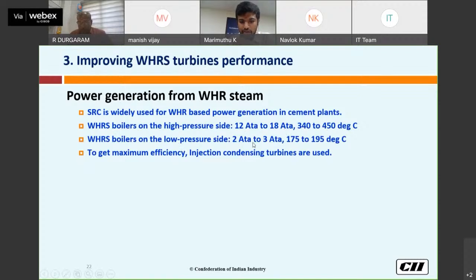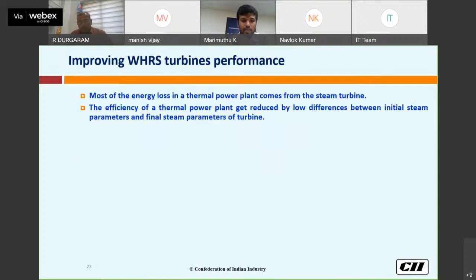And on the low pressure side, we will get up to 2 to 3 ata, that is also 175 to 195. So this is giving us an injection condensing turbine. This is given as an injection steam for power generation. So if you look into the power plant, most of the loss comes from the turbine, because there only we lose our latent heat.